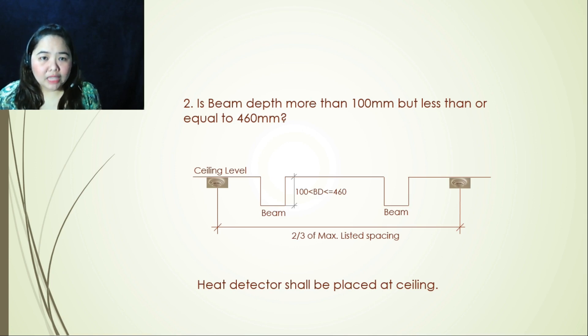Now we have our second argument: beam depth more than 100 millimeters but less than or equal to 460 millimeters. So looking at the illustration, these are your beams. If this is the case, you will then consider two-thirds of maximum listed spacing. And you cannot put your heat detector at the bottom of the beam, it can only be placed in the ceiling underside.